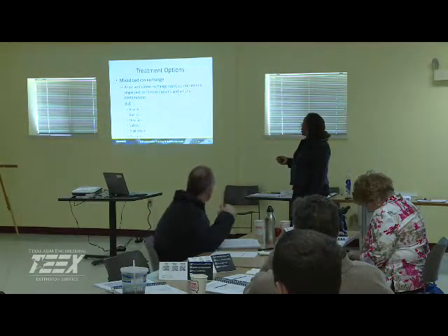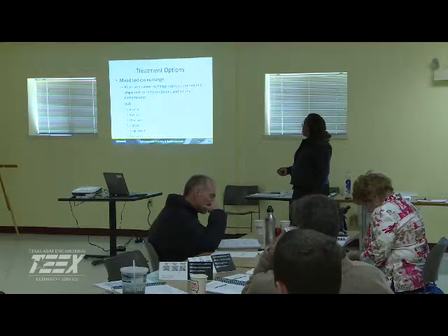Mixed bed ion exchange is another treatment option that may be available. Again, we're using anion and cation exchange combined in a single unit. It can be used for arsenic, radium, uranium, sulfate, magnesium, as well as calcium removal. Optimum pH is the high range for proper removal.